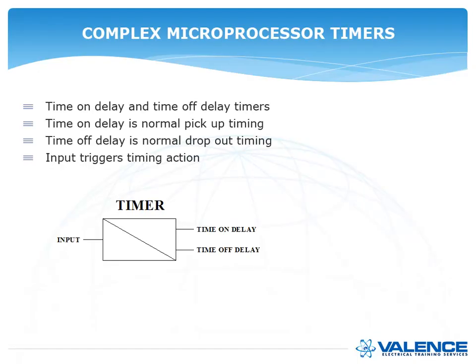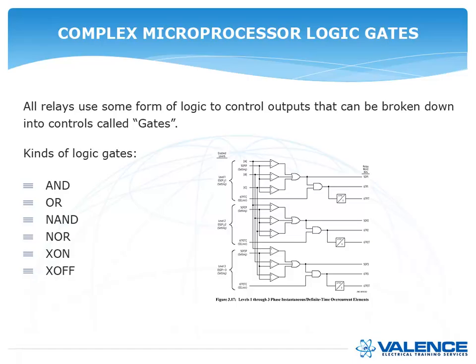Then you can have timers — a time-on delay and a time-off delay timer. The time-on delay is normally a pickup timing, so whenever that input turns on, the timer starts, and once that timer expires, the time-on delay will turn to a 1. A time-off delay is when that input goes away, the off delay timer starts, and when the timer expires, it'll send the time-off delay output. Those inputs trigger timing actions.